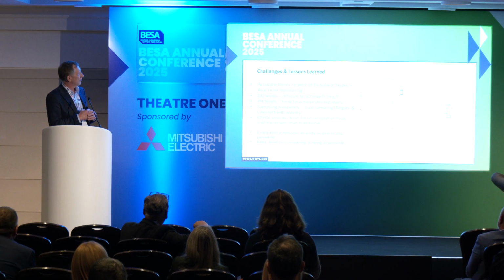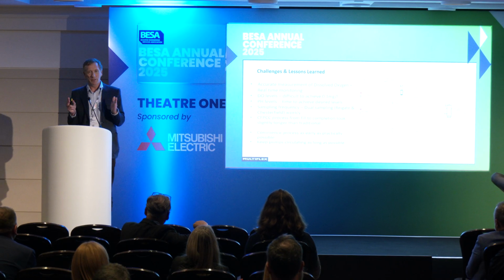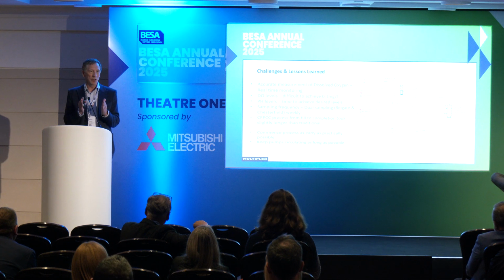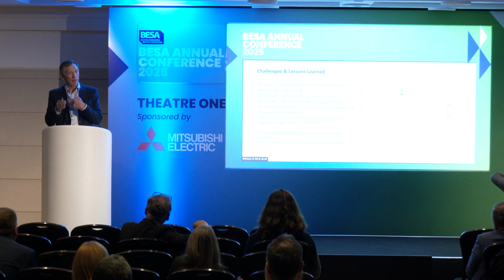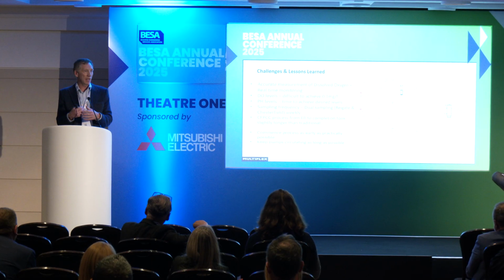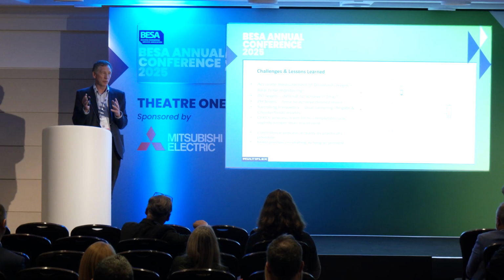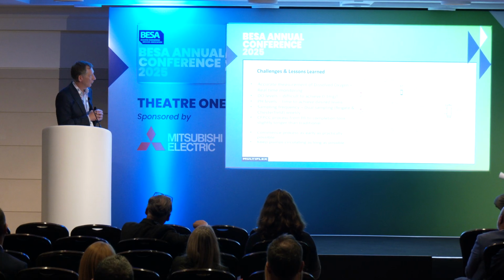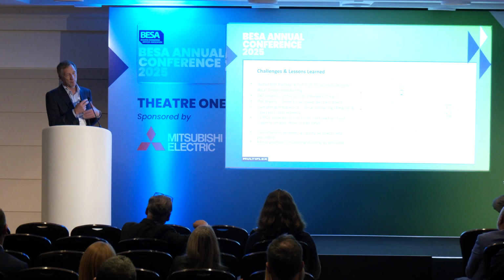We've found it difficult to achieve the 0.1 milligrams per litre target. On the Davy Street job, we probably got it down to about 0.5 by the time we handed over, but after that we kept running it through the reactor unit and it cleaned up further. So that's something we're looking at on current jobs - what level we set for dissolved oxygen - and we're speaking to specialists about it, because 0.1 is quite difficult to hit during that small construction phase.